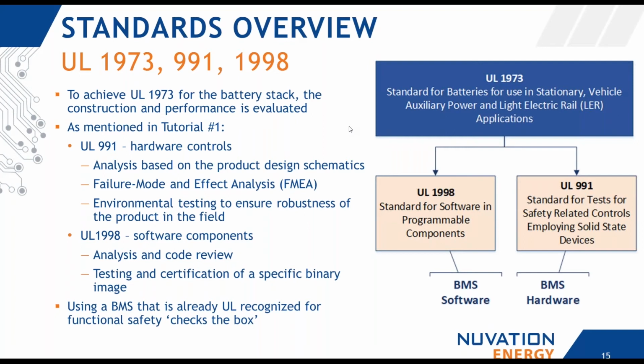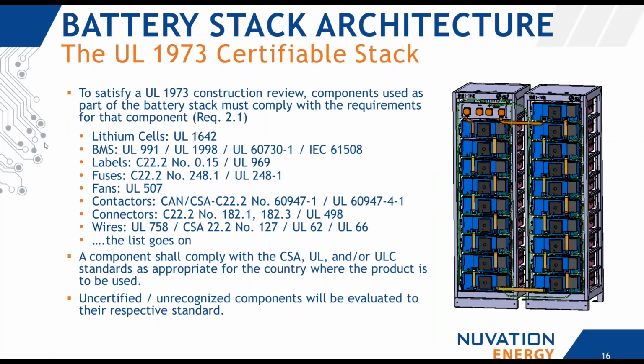UL 991 requires a full analysis, both failure mode effect analysis as well as testing. And for 1998, that's a very, very detailed software and coding review, looking at both the code itself, but also how you test it to make sure that there are no code regressions that can get in there. But by using a BMS that's already UL recognized, that checks the box. So you can skip over this large schedule and cost hit and just move up to the higher level. And it doesn't really end with BMS components.